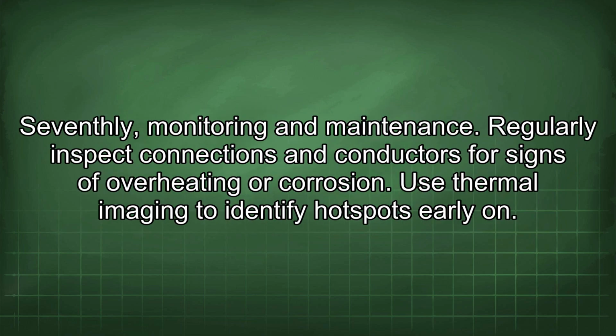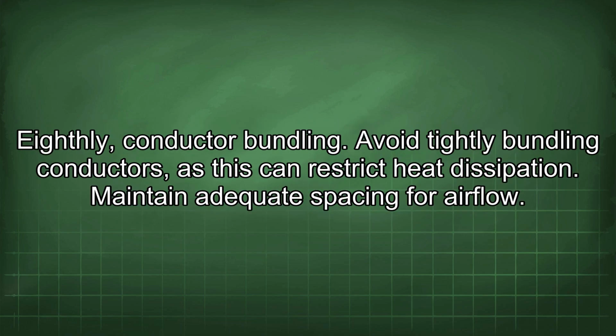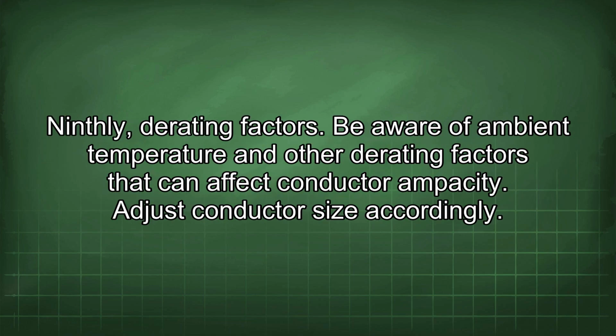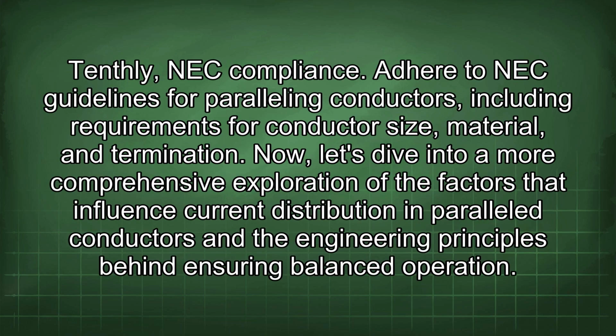Seventhly, monitoring and maintenance. Regularly inspect connections and conductors for signs of overheating or corrosion. Use thermal imaging to identify hotspots early on. Eighthly, conductor bundling. Avoid tightly bundling conductors, as this can restrict heat dissipation. Maintain adequate spacing for airflow. Ninthly, derating factors. Be aware of ambient temperature and other derating factors that can affect conductor ampacity. Adjust conductor size accordingly. Tenthly, NEC compliance. Adhere to NEC guidelines for paralleling conductors, including requirements for conductor size, material, and termination.